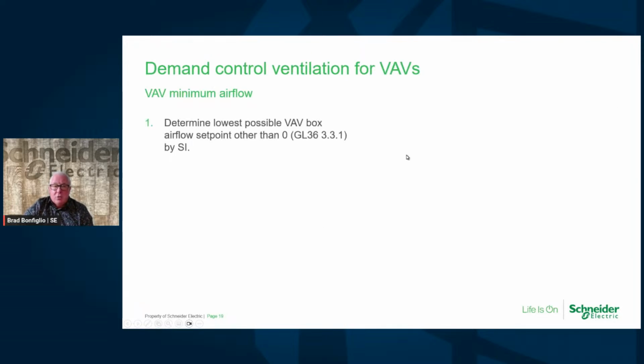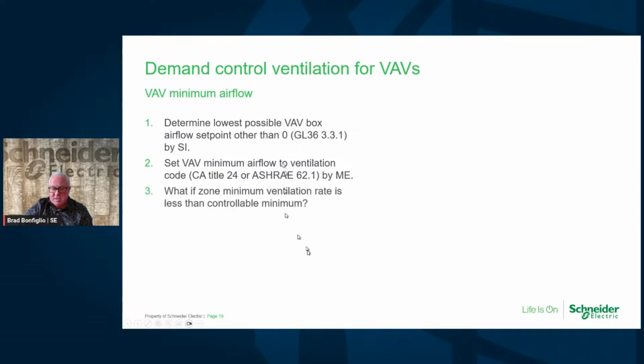So when you're determining demand ventilation, you want to look at, again, we kind of talked about the lowest VAV box and what the airflow set point is. And then what you're going to do is set up the minimum airflow. And again, there could be Title 24, it could be ASHRAE 62.1. That's typically set up in the control drawings by the mechanical engineer. The lowest possible VAV set point other than 0 is typically set up when you're doing the setup of the programming. And I'll explain what this means in a second.